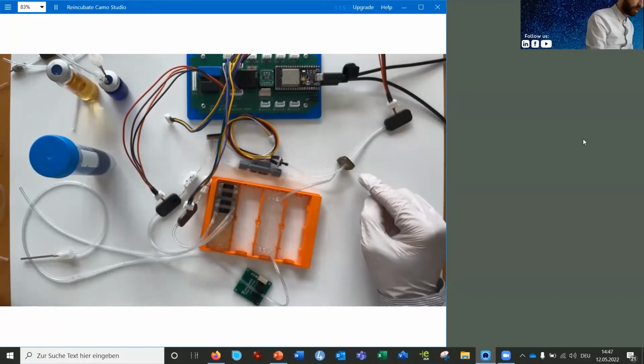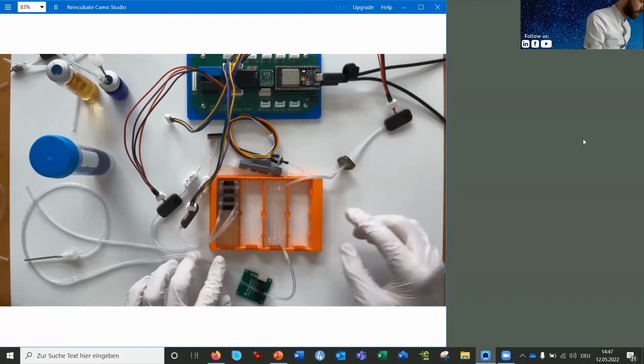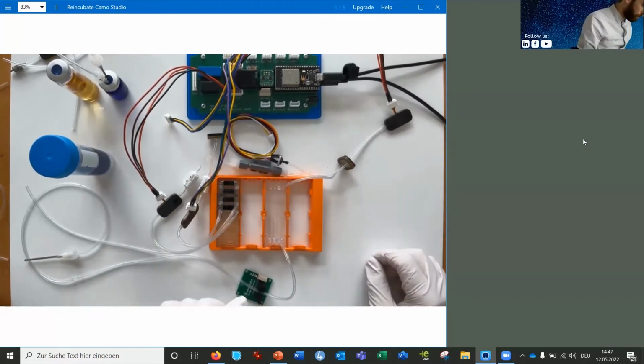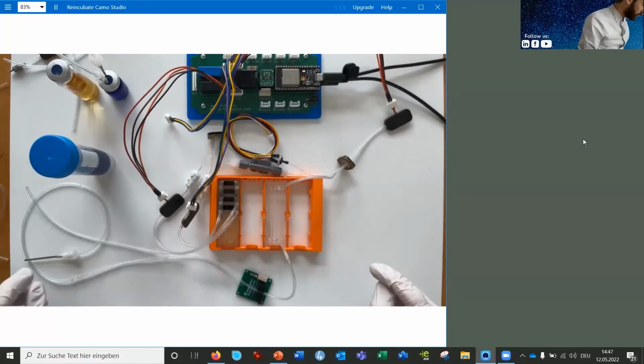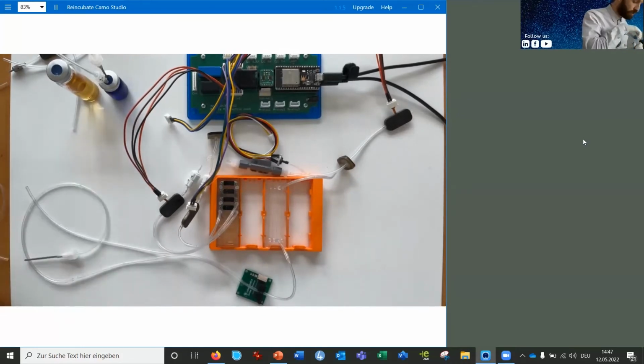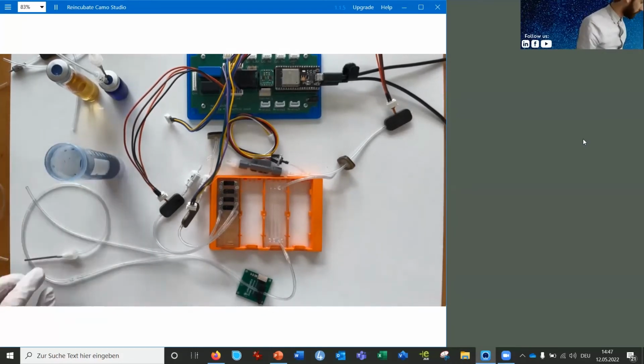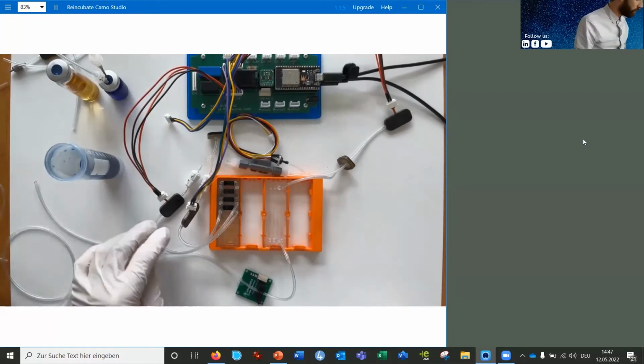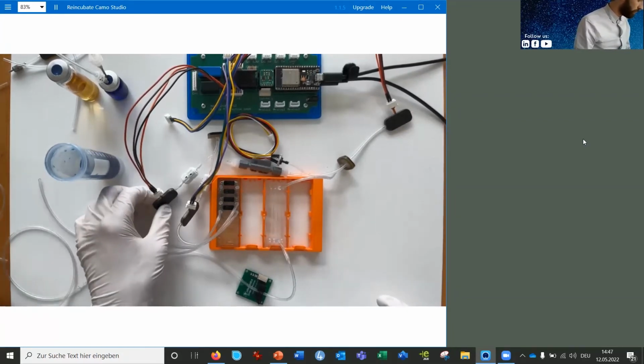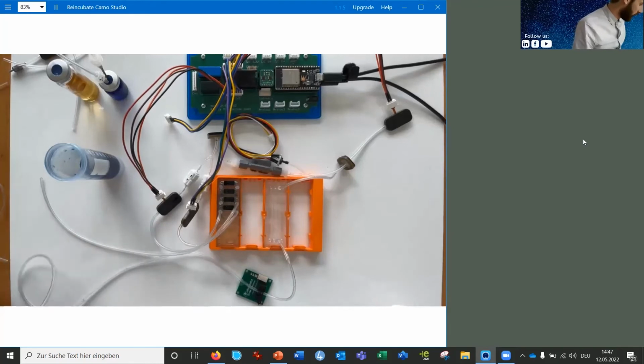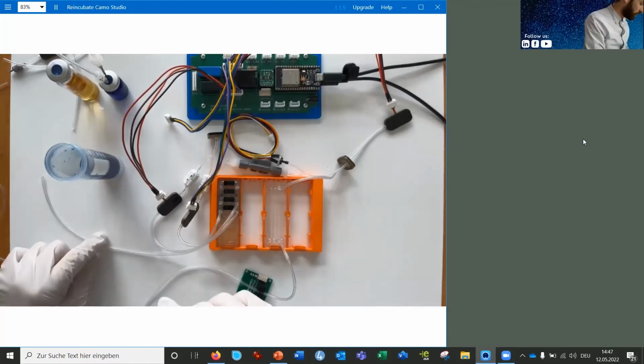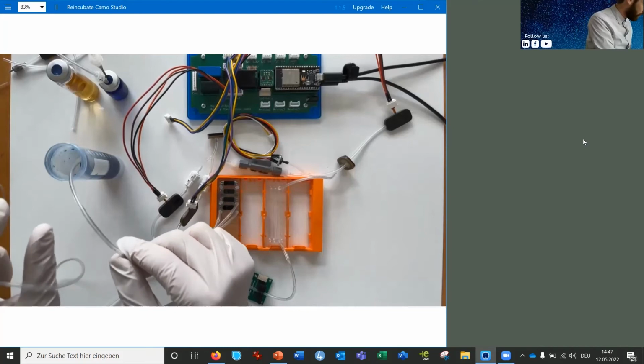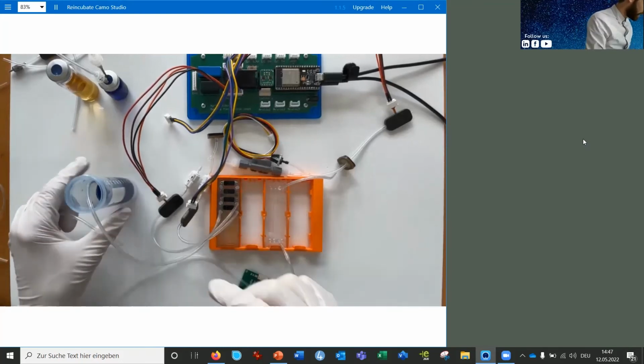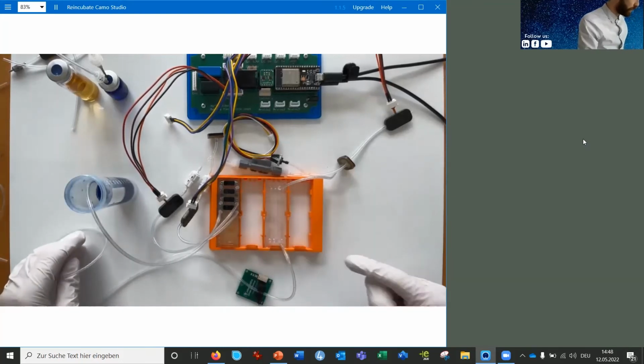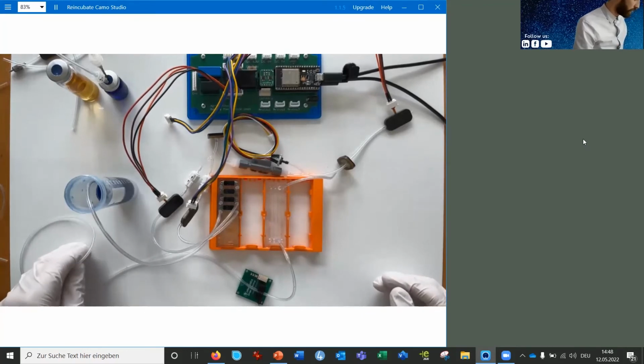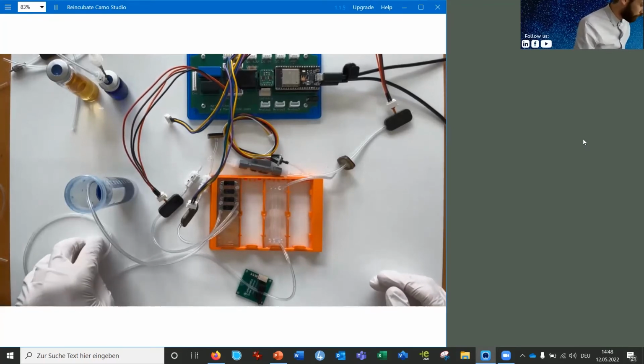This pump actually runs a bubble trap, which you will see in a second. The two pumps are connected to the Mimetus valves, so I can distinguish between them. By the way, the micro pumps are able to pump liquids and gases. This is what I want to share in the demo, I want to run liquids and gases, and that's why I'm using the Mimetus valves to distinguish between those two fluids.